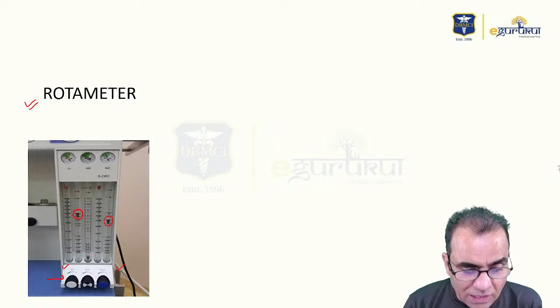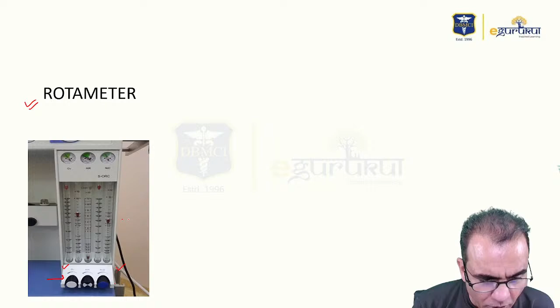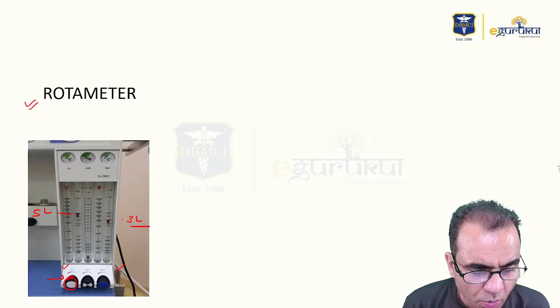Say I want to switch on oxygen, and by mistake I don't open nitrous oxide. Just to give visual safety, they made them color coded, and you can see black for air. That I told you, this is the bobbin. I think you're not able to see it from here. Otherwise, you can see the flow also, like here. Nitrous oxide is flowing at a flow rate of 2 liter, 3 liter, approximately 3 liter. And oxygen we are seeing here is 1, 2, 3, 4, 5 liter. If I want to increase oxygen, I will rotate this knob. More gas will come, and the bobbin will go up. If I want to increase nitrous oxide, I'll rotate this knob, more nitrous oxide will enter the tube and the bobbin will go up. That is how we can set the flow rates.